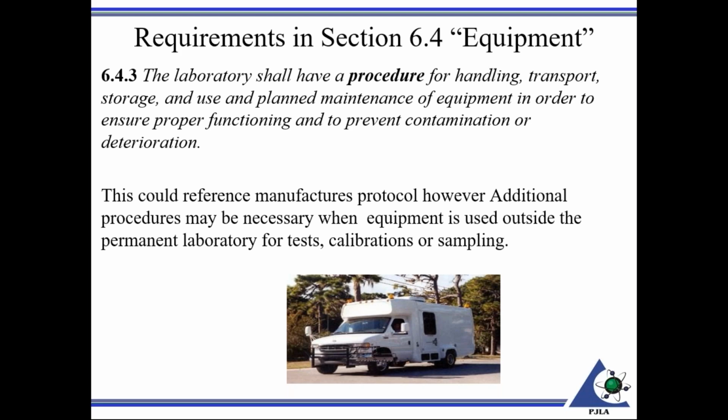Or if you're a facility that regularly takes your equipment, say, off the premises on site, additional procedures may be necessary to assure equipment is packed securely and transported in a manner that would maintain the integrity of its traceable calibrations.